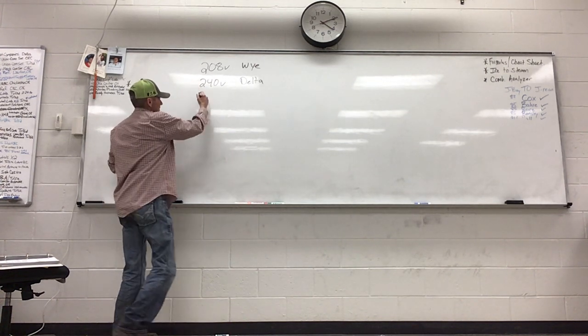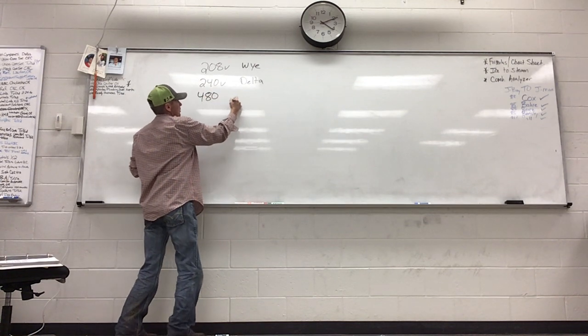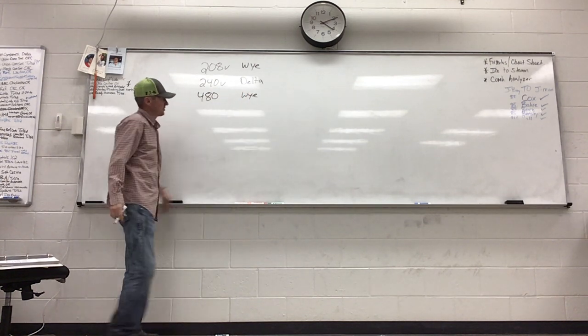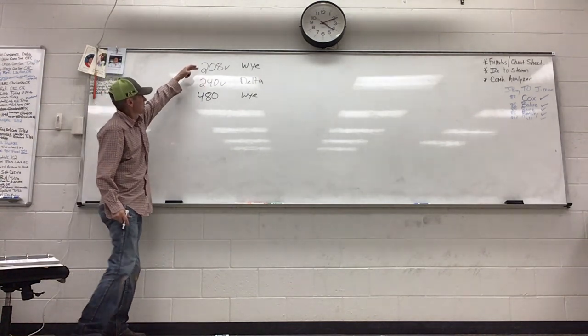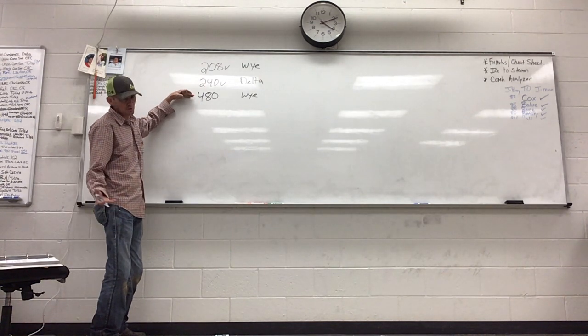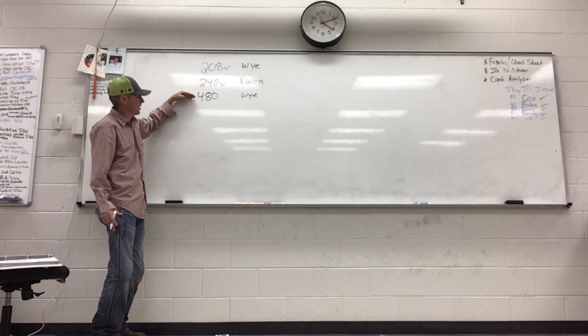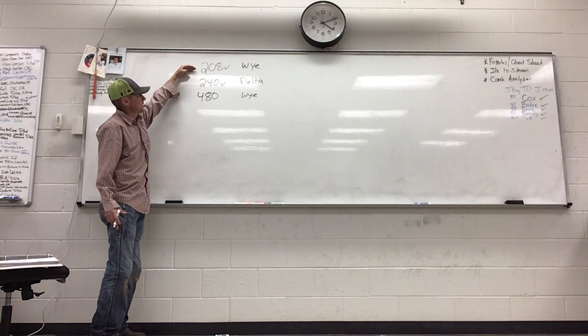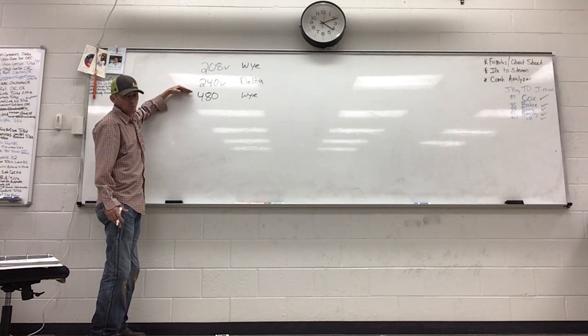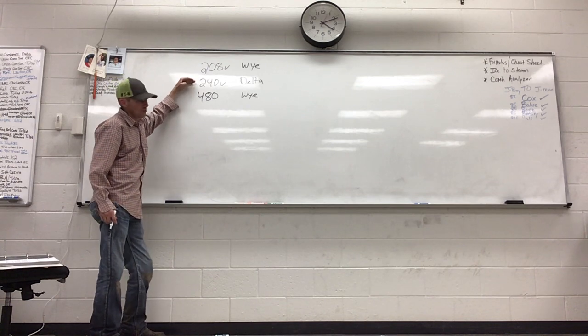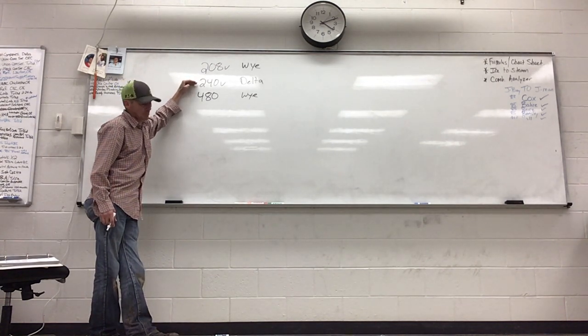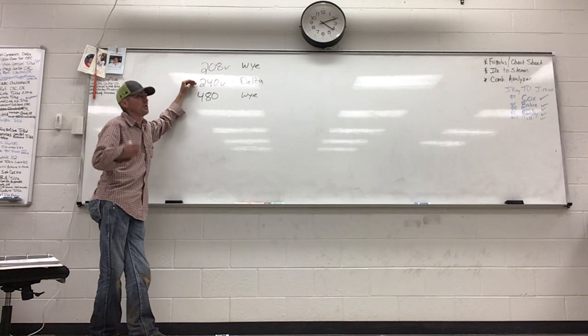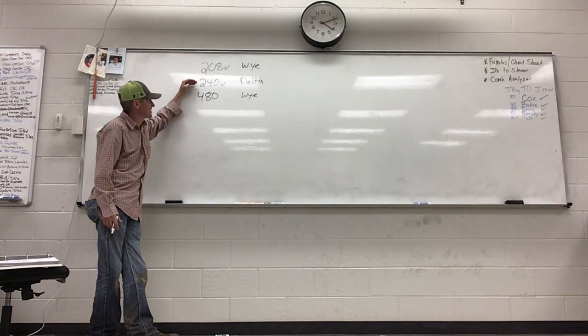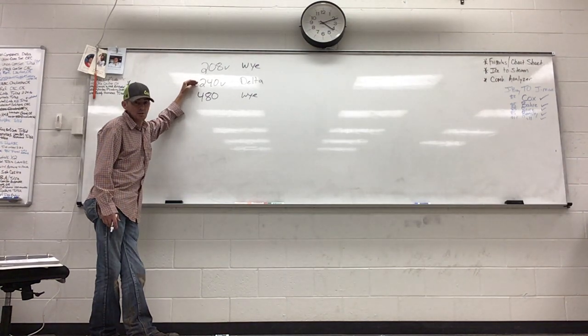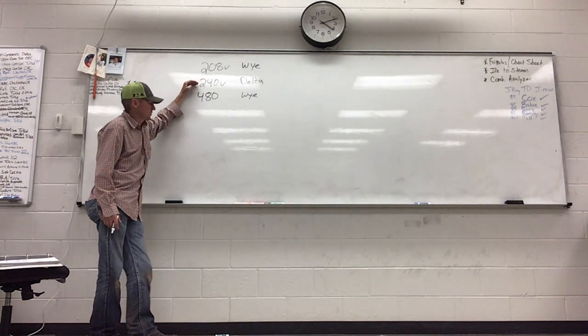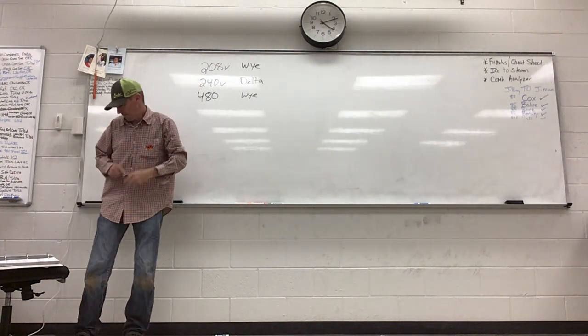And then the final one, we're going to talk about 480 volt. There's the phone. It also comes off of a Y transformer. So our 208 and our 480, or 460, whatever you want to call it, 460, 480, same thing, both of these come off of a typical Y transformer, where the 240 is going to come off of that center tap delta. This is the one where we're going to have the stinger leg, the hot leg, the widowmaker, whatever. Like I said, not near as common, but they're out there, and for sure out there. All right. And I got my cheat sheet right here.